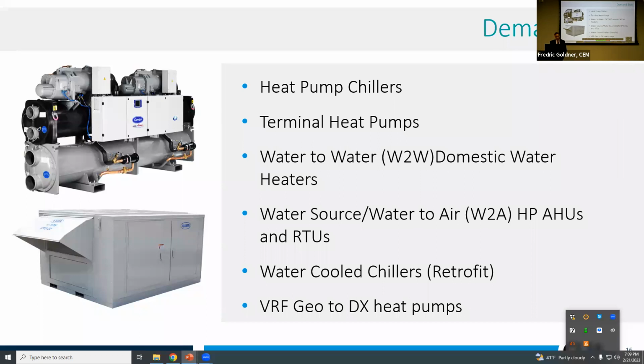I've designed those systems a lot. This is not what we're talking about. Those are great systems. I call them high inertia. What I mean by that is that because it's direct exchange and the refrigerant is in direct contact with the ground through copper pipes, at startup the ground literally is going to have to play catch up to the compressor, because it's so efficient and it's pulling the energy so rapidly out of the ground. And that's good. I'm making the ground immediately colder in your loop when your compressor starts.